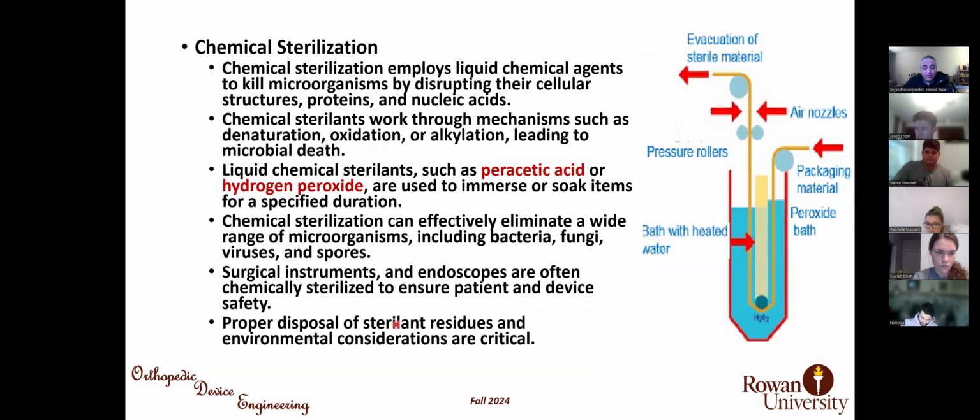And we have a chemical sterilization, which is very common in the surgical field. Sometimes you have devices that you don't have time for re-sterilization. For example, you have a metal grasper, and you are using it and finally drop it. If you want to send it for sterilization, it takes at least 1 hour, and you don't have time to wait for it. You don't have a replacement for it. So the best way is for that single device, you use chemical sterilization.